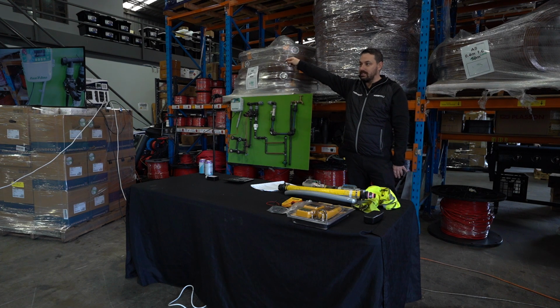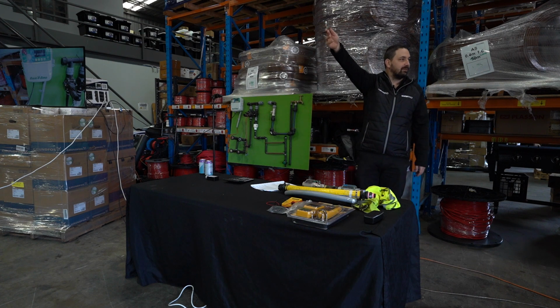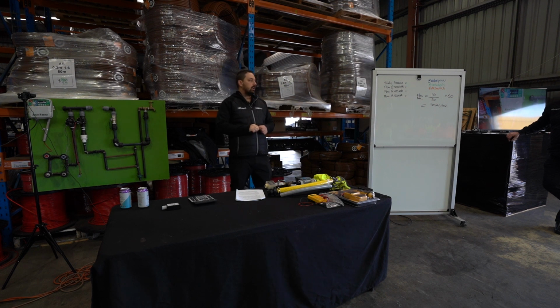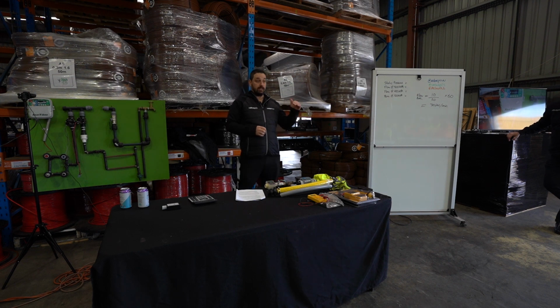You get out to the west, traditionally we'll see, like Morphett Vale. Well, that's where we've had the biggest issues, is Morphett Vale. Yeah, those 200 kPa kind of. Yeah, we're seeing some systems where static pressures are 250 to 300 kPa at static.